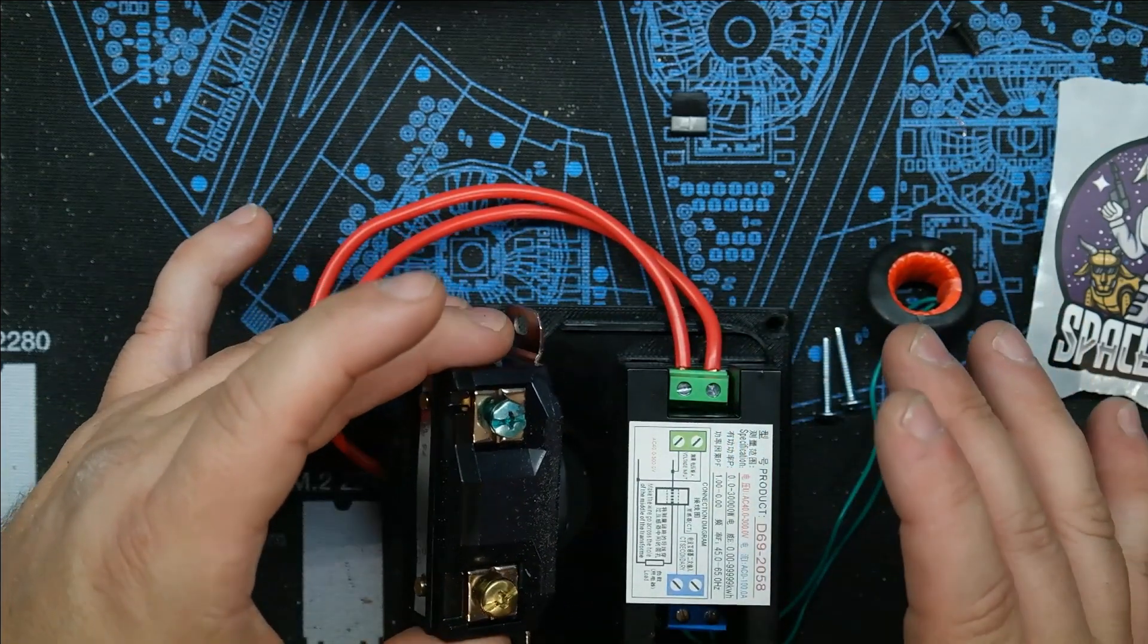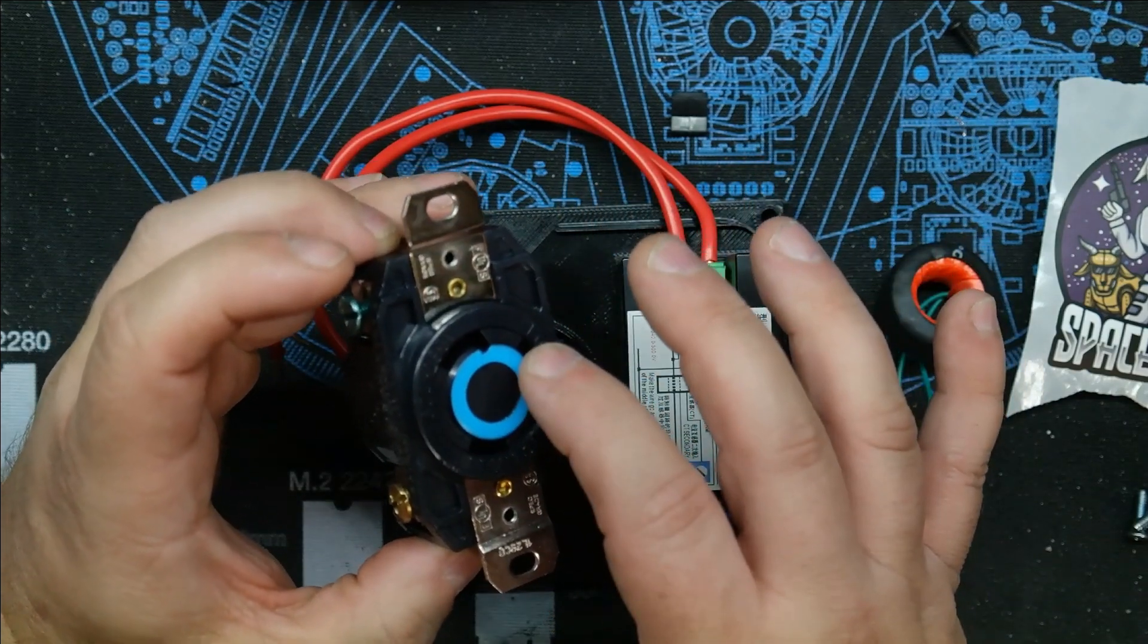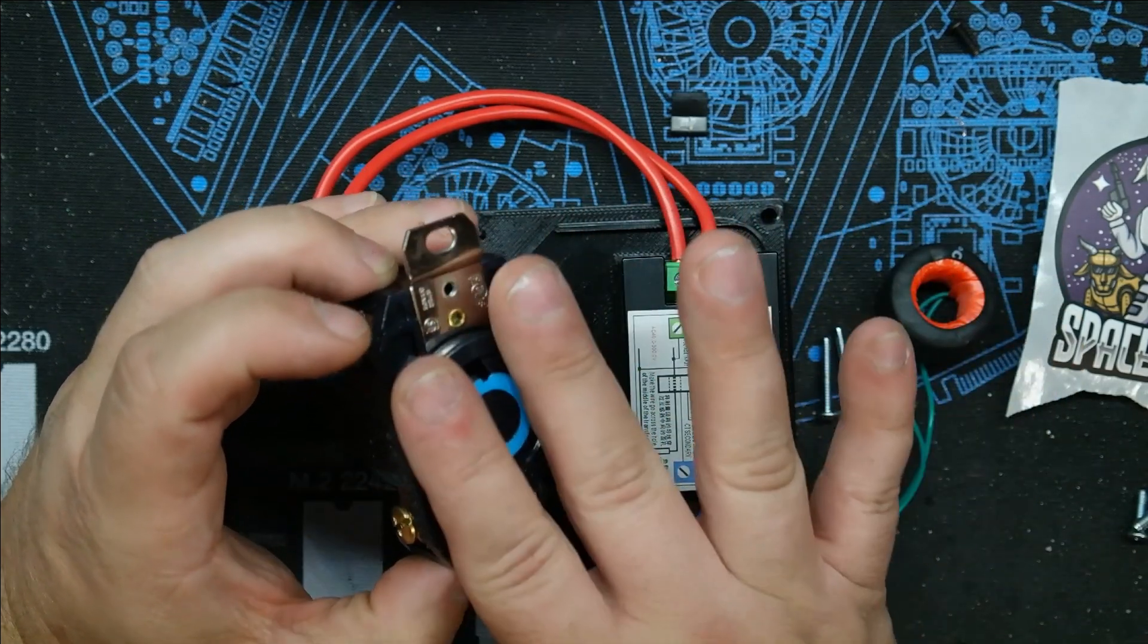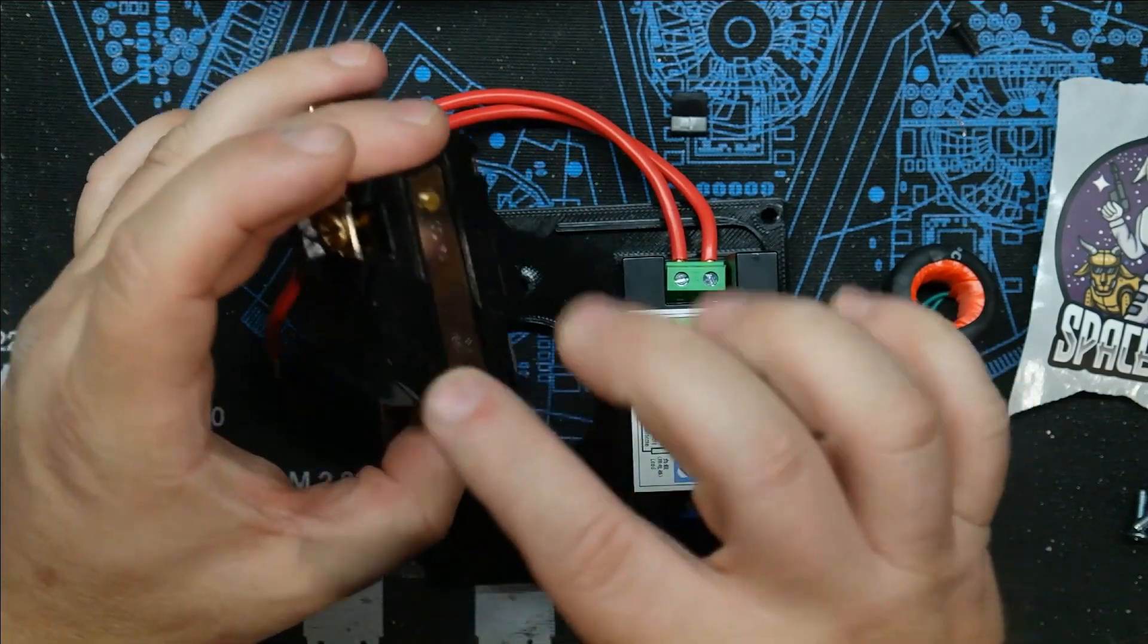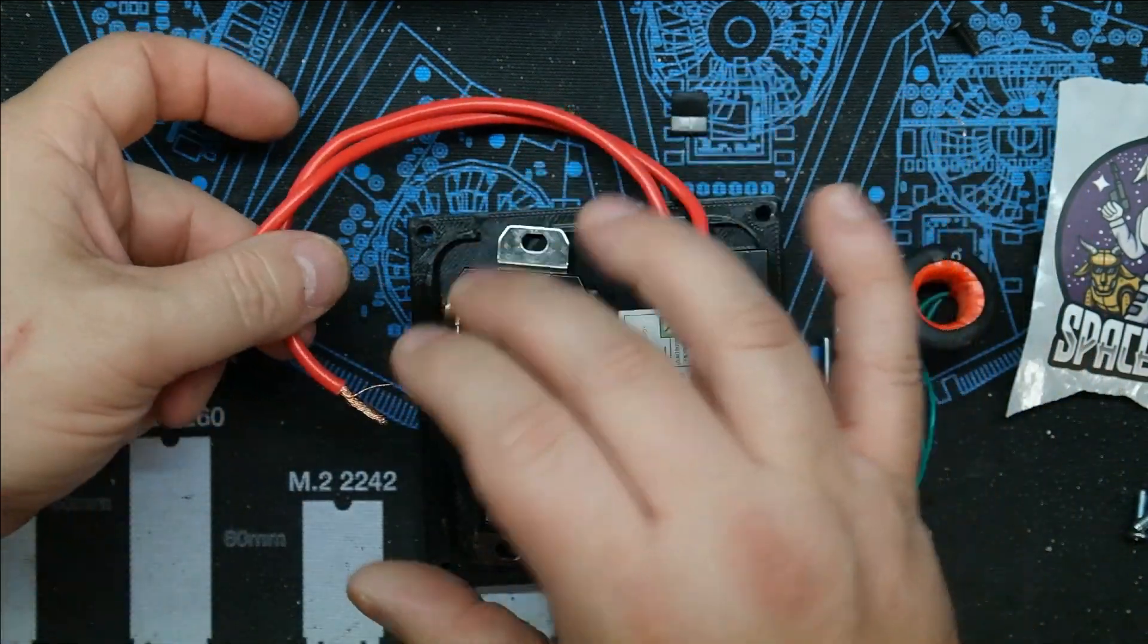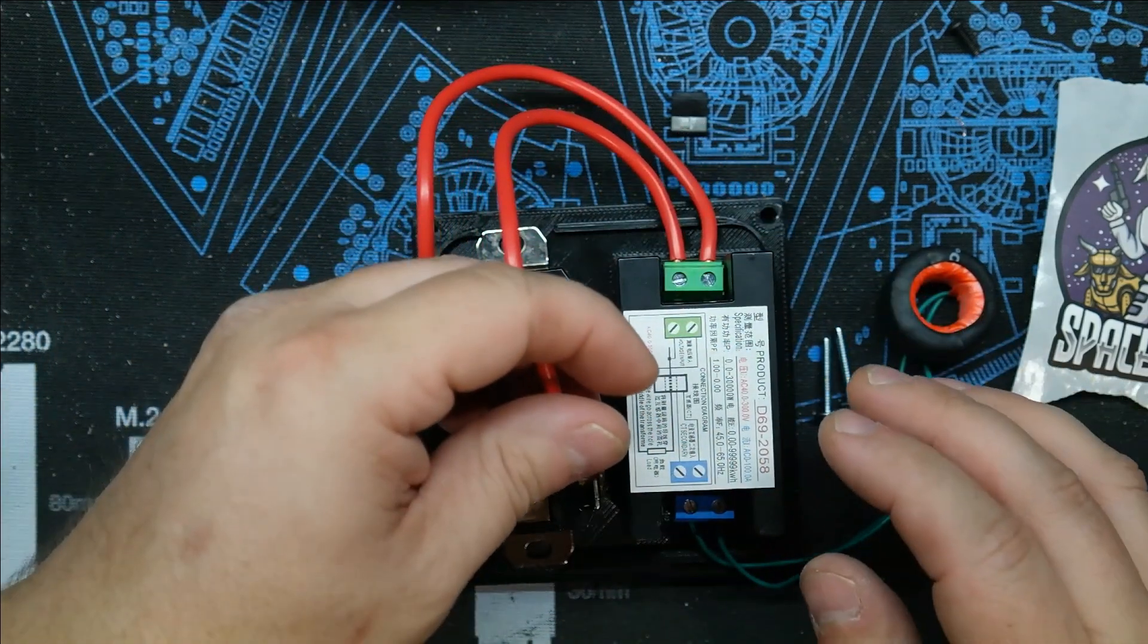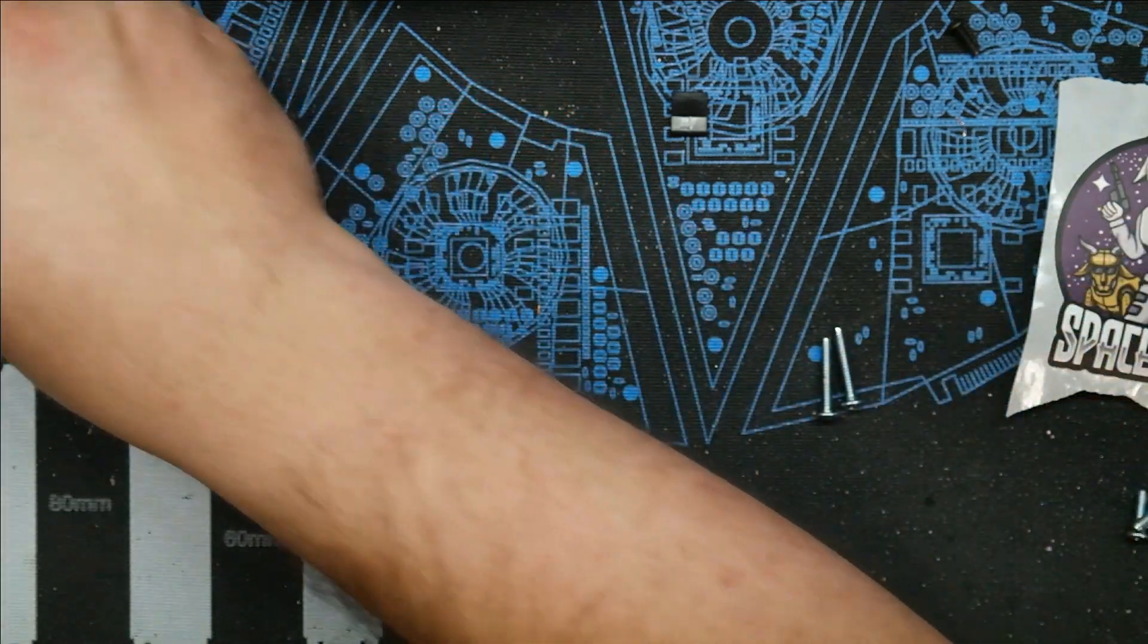Now that we have this out, the L6-30 plug has three conductors: two hots and a ground. There's no neutral in this unit - that would be for a dryer outlet which has four conductors. We're only messing with three. You have green ground, hot one, hot two. Doesn't matter which hot is hot, they're both hot.